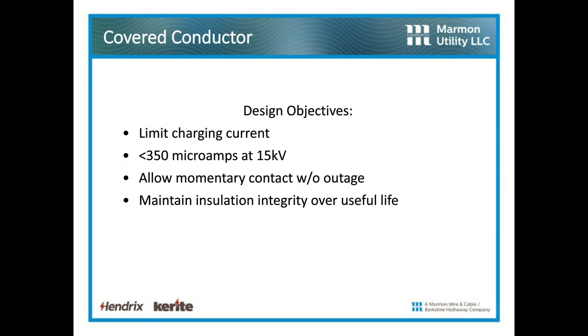Our design objective is that, in general, we try to limit that charging current on the surface at 15 kV to 1/3 of a milliamp, so 350 microamps. To put that into perspective, we need, say, 7 to 10 milliamps to fibrillate the human heart. So at 1/3 of a milliamp, we've got about 5% of the fibrillation threshold. So is it dangerous? Yes. Is it fatal? No. And that 1/3 of a milliamp on the jacket allows momentary contact without an outage, and it's not going to damage the insulation over the useful service life of the conductor, which is of tantamount importance for a long, useful service life.